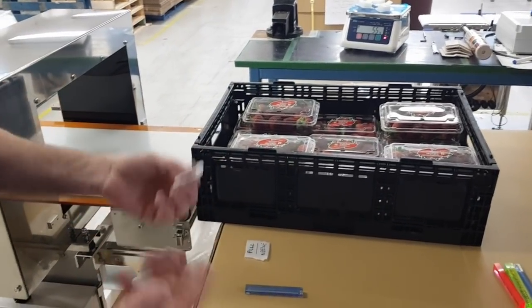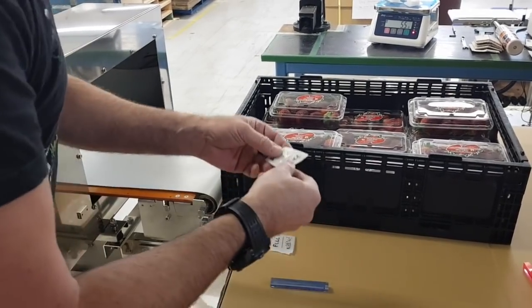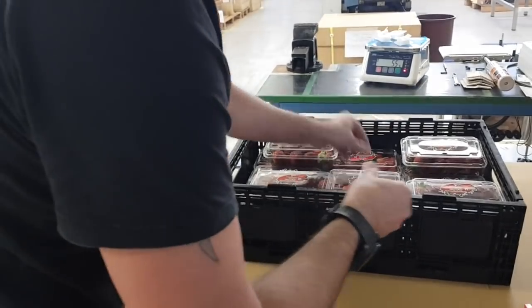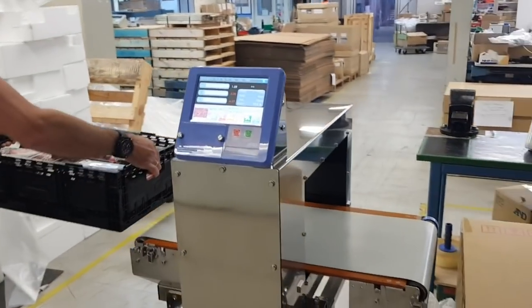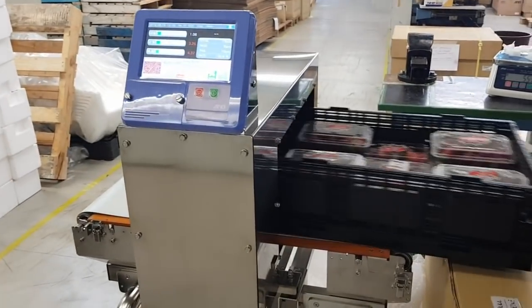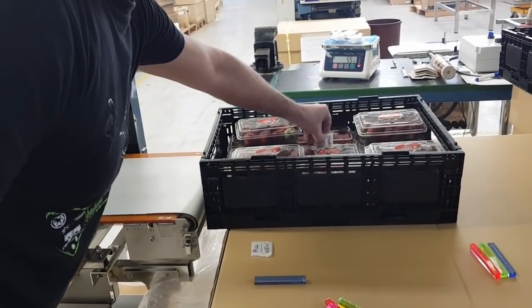Obviously you have no control over which way a needle contaminant — if someone's put it in there — is going to be oriented, so you just need to be mindful of that restriction. I'll put through the half needle now in a lengthways position — we can detect that no problem.